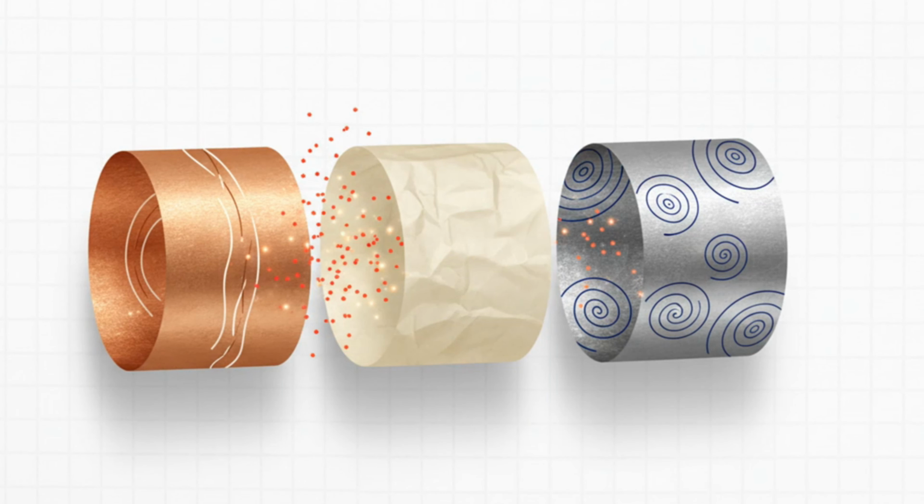But hold on, the losses don't just stop at the conductor. The insulation, the dielectric, it generates heat too. And that metallic sheath around the cable, it can act like the second part of a transformer, with unwanted currents getting induced in it from the main conductor's magnetic field. These are called eddy currents and circulating currents. And yep, they create their own heat, adding to the total energy loss.